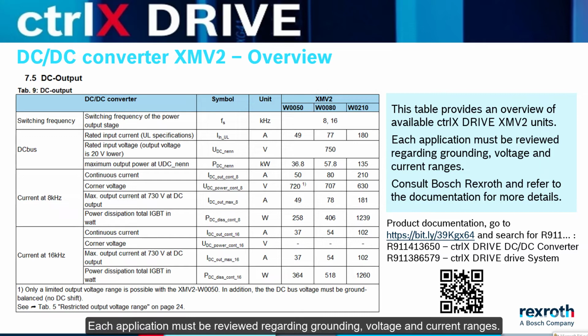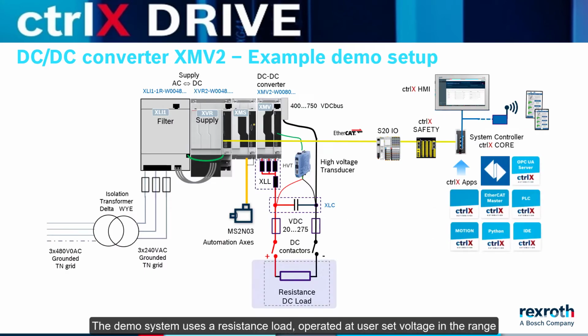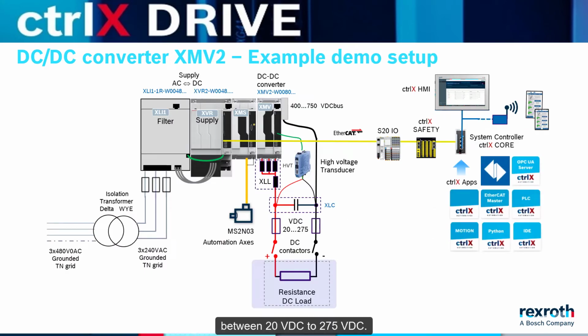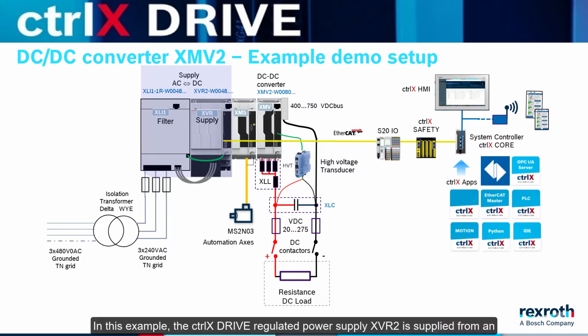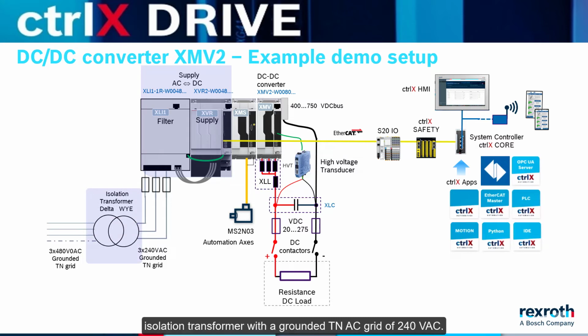Each application must be reviewed regarding grounding, voltage and current ranges. Consult Bosch Rexroth and refer to the documentation for more details. The demo system uses a resistance load, operated at user set voltage in the range between 20 to 275 volt DC. In this example, the ctrlX drive regulated power supply XVR2 is supplied from an isolation transformer with a grounded TN AC grid of 240 volt AC. This allows the user to choose the DC bus voltage in the range between 400 to 750 volt DC to best meet the application requirements.